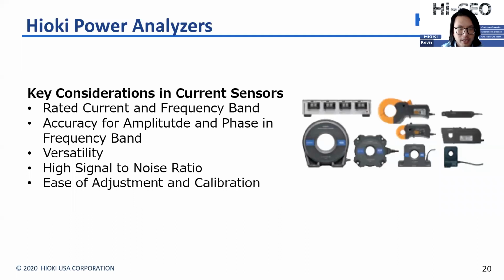So what we need to keep in mind is the rated current and the frequency band. For us to measure the current with a high degree of precision, we need a sensor that is rated for the magnitude of the current target. Also, all of the sensors that we have at HIOKI are rated as RMS values, while many of the other ones are rated using peak values. It's also important for us to verify that all the frequency components of the current can be measured are included in that bandwidth.